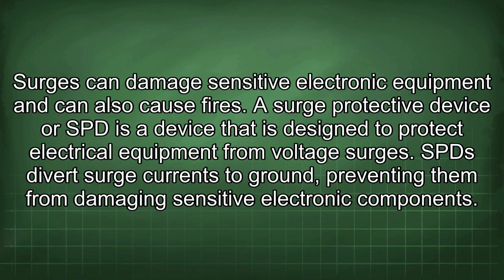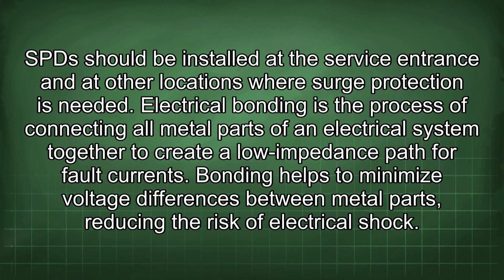A surge protective device, or SPD, is a device that is designed to protect electrical equipment from voltage surges. An SPD diverts surge currents to ground, preventing them from damaging sensitive electronic components. SPDs should be installed at the service entrance and at other locations where surge protection is needed.